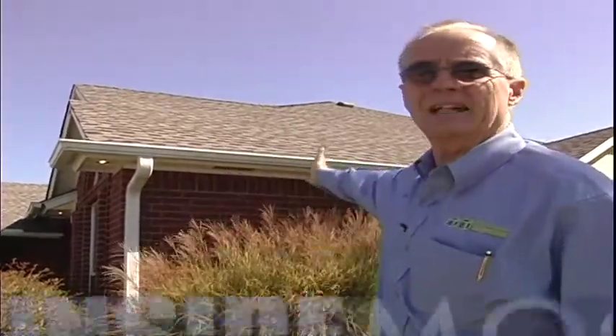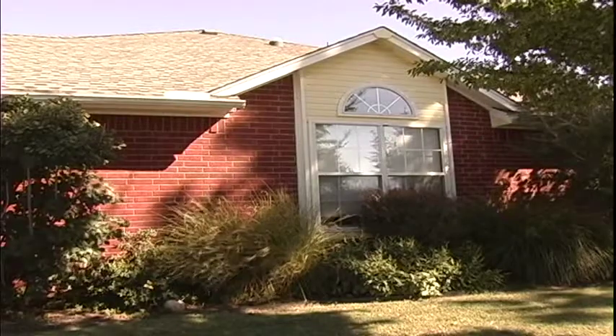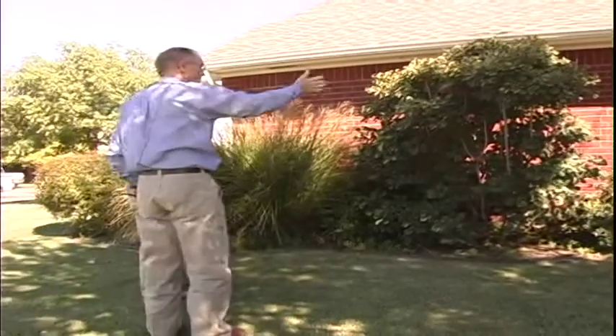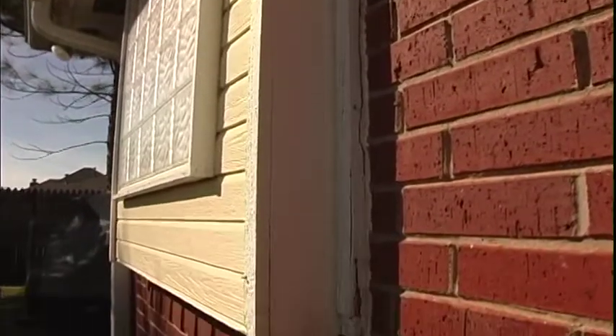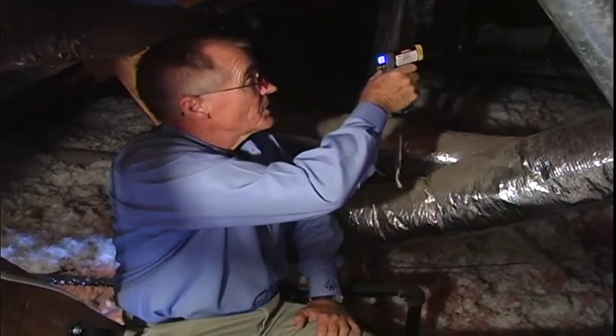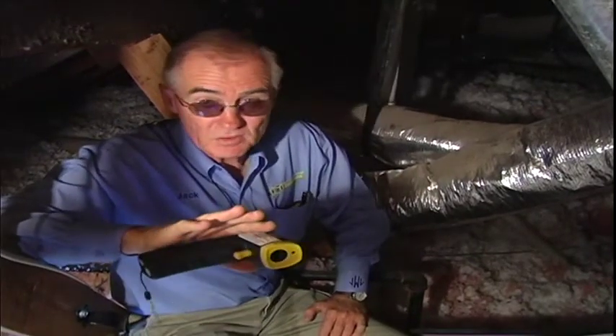One of the first places Jack starts is the attic. If it's 66 degrees outside, ideally we'd like it to be 66 degrees in the attic. He doesn't want to see plastic over the turbine vents in wintertime — he wants great ventilation year-round and great insulation. In this particular home, that wasn't the case: readings in the attic were 93 to 96 degrees, about a 30-degree difference from outside. Once we get 20 or more degrees of difference, the attic is not operating as efficiently as it could.